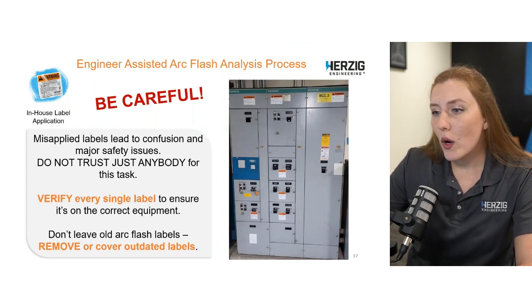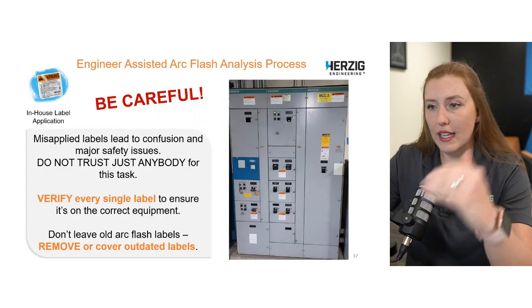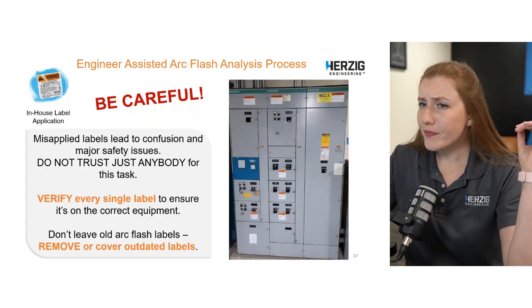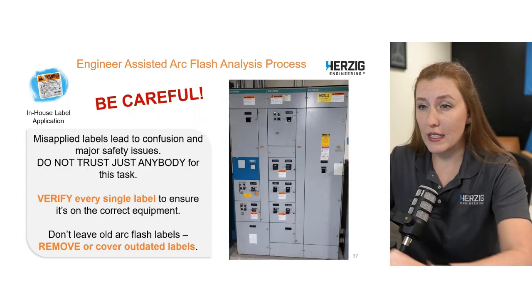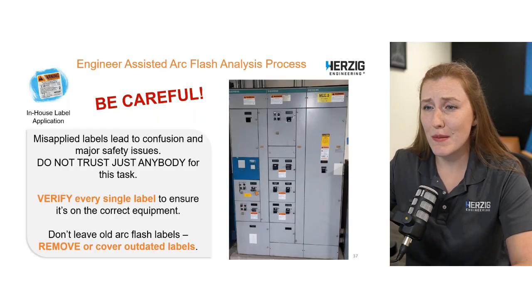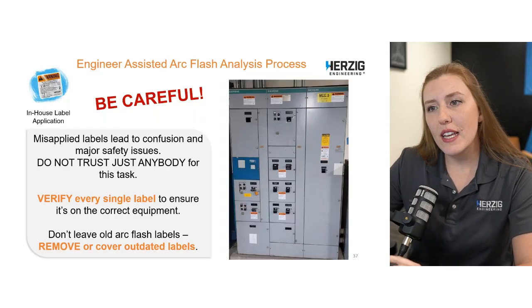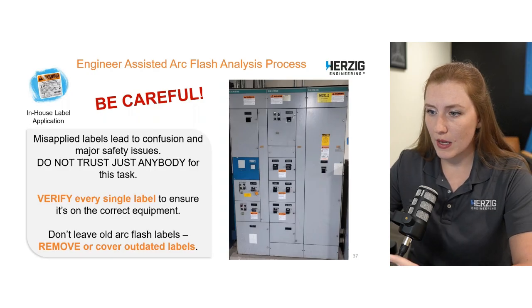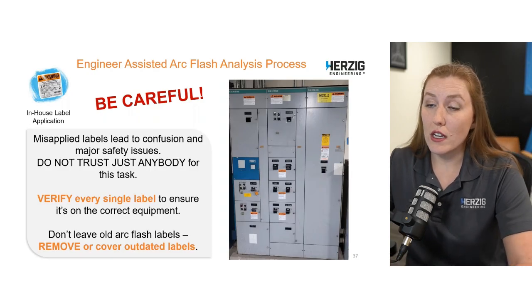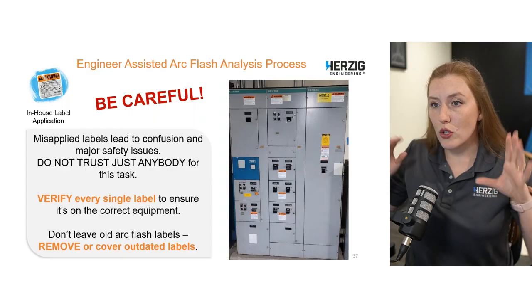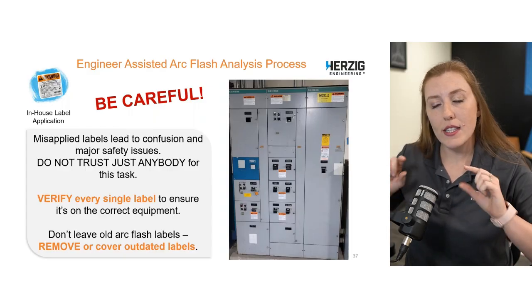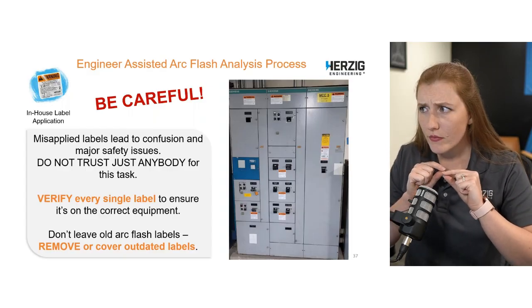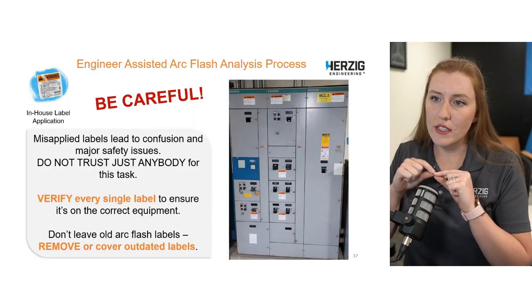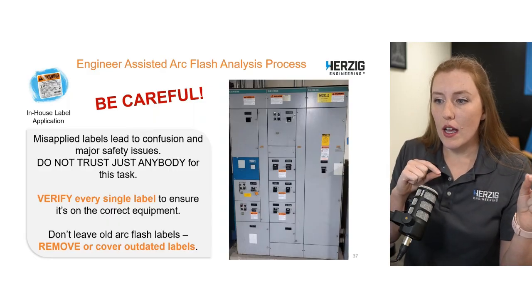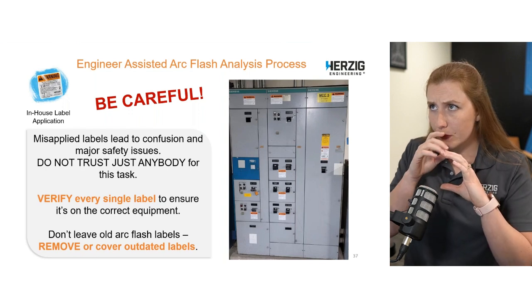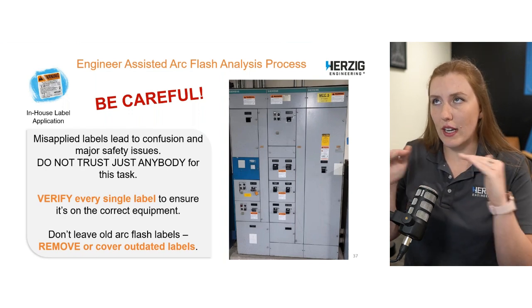Okay, now for that labeling practice, it's going to be on the outside, it's going to be eye level. And it should be where we tell you, essentially, match the name to the equipment, such and so forth. For things like automatic transfer switches, and this is coming from a question, where there's a normal and an emergency feed, the labels usually will go on the ATS, and it will mention whether it's from emergency or normal feed. So, or it could be directly downstream of the ATS.